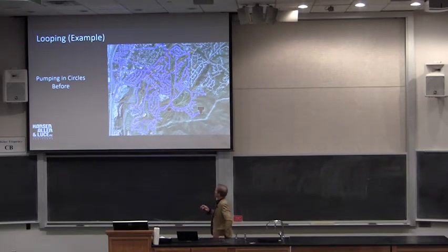This is actually North Salt Lake. This is the top of their system, and here's a tank up here, and here's a pump. This goes down the hill here, and they have lots of pressure zones, 1, 2, 3, 4, 5 pressure zones, where they pump water all the way from down here to the top of the city. And so we actually showed this example to the city council and the engineers to show them what was going on.